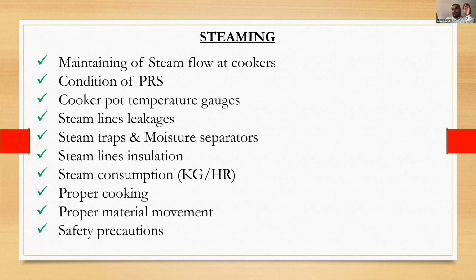For example, if it is a 1 ton boiler, the consumption is 250 kg per hour. 250 kg per hour means it will continuously take 250. If we have 4 cookers, this 1 ton boiler is enough for that. So we have to coordinate with the OEM and the boiler people, and then we will come to know what the consumption is.